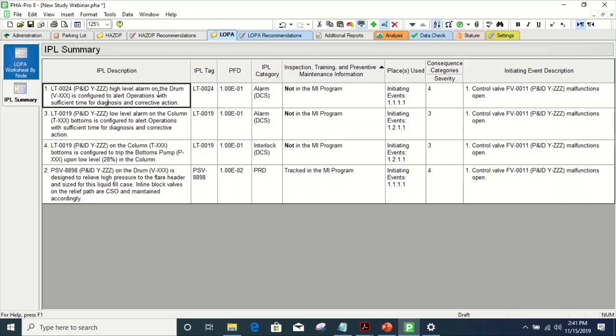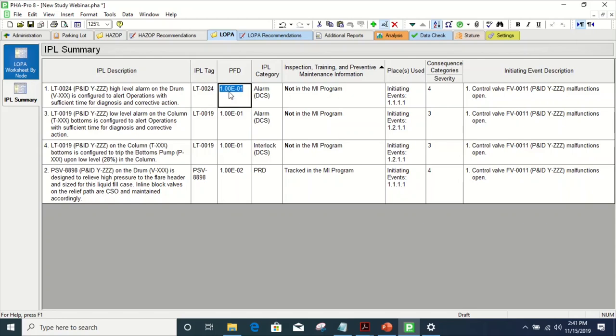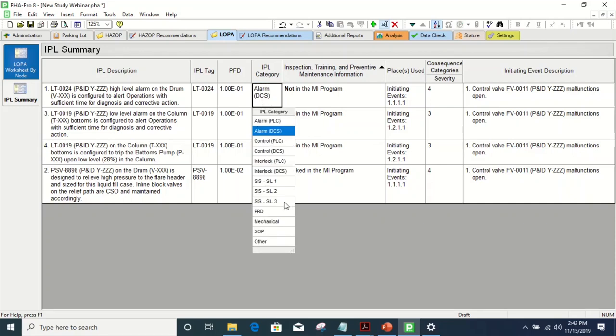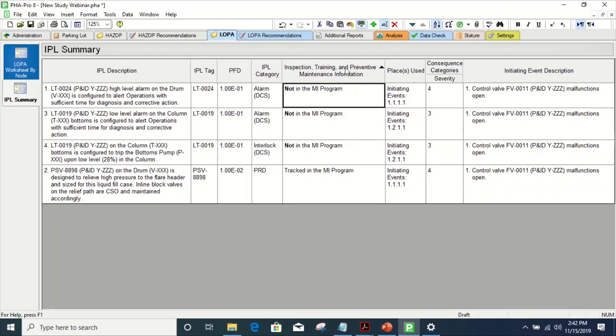This is a high-level alarm configured to alert operations with sufficient time for diagnosis and corrective action. We have the tag number here — it'll be useful later when we print this sheet, as it'll print all these columns. If you print it to Excel, which I'll go through later, you'll be able to filter by tag number or any column. Here we have our probability of failure on demand and our IPL category — what kind of safeguard this is, whether it's an interlock, mechanical trip, or pressure relief device. Here's a very useful column specifically for what we're talking about: our mechanical integrity program column. We can document whether it's in the mechanical integrity program or whether it's not.